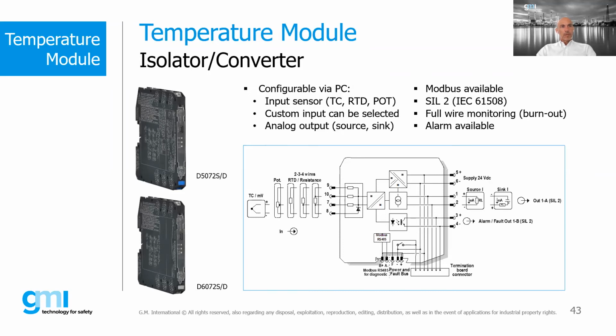So, the temperature modules, isolator and converter. There was a question: what are the differences? An isolator is just a unit that isolates input to output without any modification, while a converter, or signal conditioner as I call it, is converting the signal into another standard, in this case from thermocouple or PT100 to 4-20 milliamps.